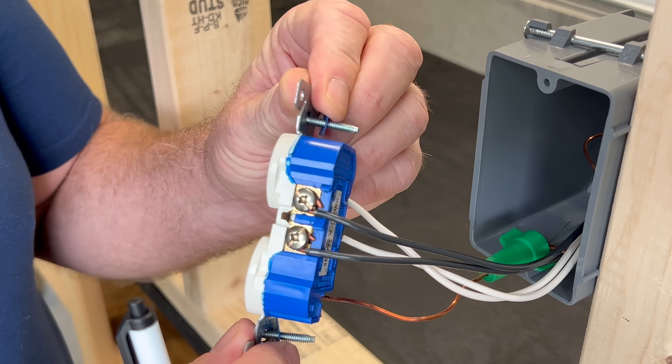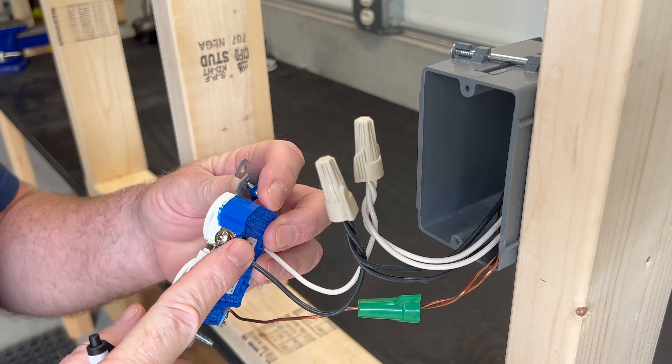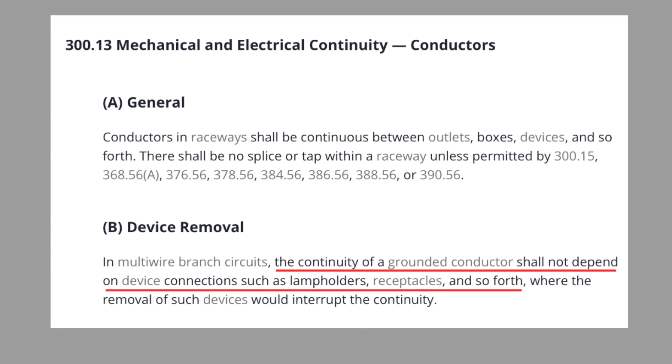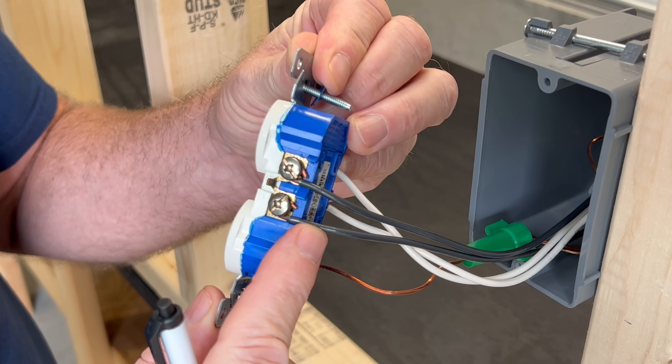False claim number one: electrical pigtails are required by code. When we wire receptacles, we have two code-compliant methods to choose from. We can through-wire, which is when the incoming and the outgoing wires are connected through the device itself, or we can pigtail, which is splicing the incoming and outgoing wires together with tails that connect to the device. Both methods are code compliant. Some electricians get this wrong because they misinterpret code article 300.13(B), which prohibits the neutral wire from connecting through the device on multi-wire branch circuits. A multi-wire branch circuit has two or more ungrounded hot conductors with voltage between them returning on a common grounded neutral conductor. A single circuit feeding outlets is not a multi-wire branch circuit, and pigtails are not required.